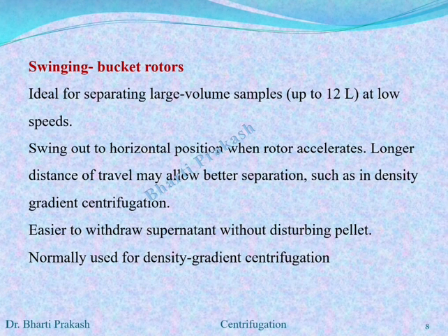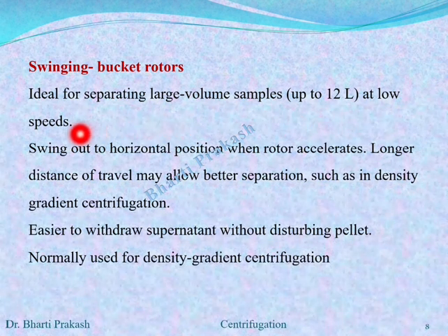And the third type of rotor is the swinging bucket rotors. As against the fixed angle type of rotors we have seen above, these rotors have buckets that swing out to a horizontal position when the rotor accelerates. It is ideal for separating large volume of samples up to 12 liters at low speeds.